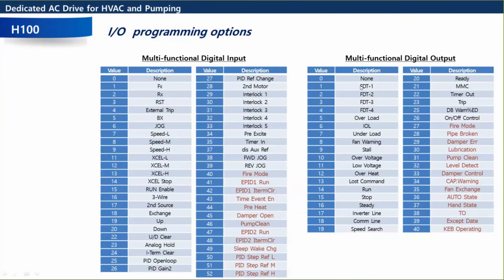We have frequency detection. That's this FDT. So frequency detection 1, 2, 3, 4. That's different levels and bandwidth for the detection of what the drive is running at. Then we have our overload, underload, fan warning. Pretty much anything that we have a trip for, you could program an output to trigger.